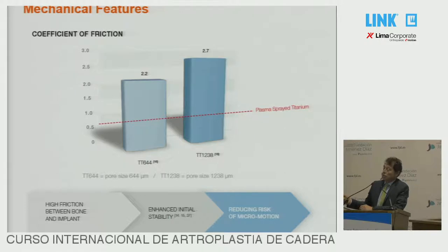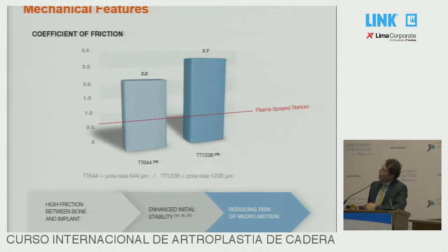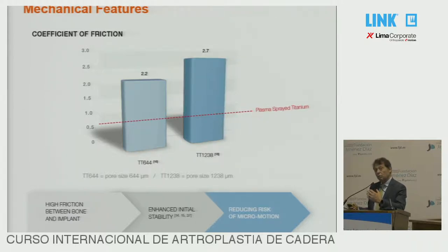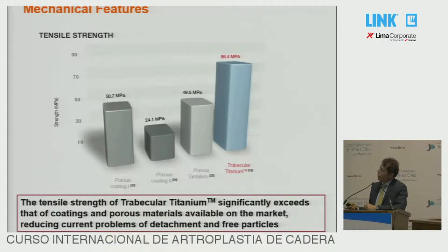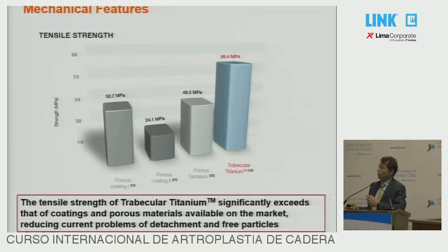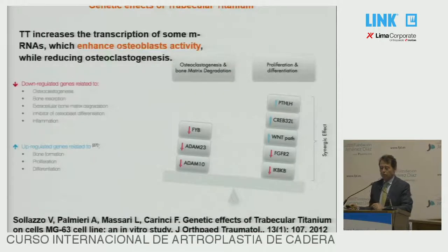This is trabecular titanium with double porosity. You will see the double porosity in the augments used in revision cases. The augments have exactly the double porosity, but this is not for biological purposes — it's for engineering purposes only. Being an augment, a porous structure with no bulky supporting structure needs double dimensional porosity for cleaning of the structure. The tensile strength is also extremely good and exceeds that of coatings and other porous materials available on the market.